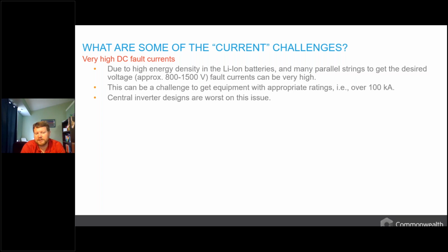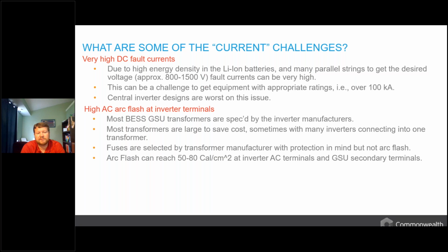So we see typical ranges that the inverter manufacturers are targeting for DC maximum voltages. The problem is, if we're limited to 1500 volts and we're talking about megawatt size long duration batteries, the only way to get the energy required is to add more and more batteries in parallel. What happens when you do that is, under short circuit conditions, these lithium ion batteries are very low impedance, and they can result in very, very high fault currents. The only thing that really protects us, or even limits us a little bit, is the collector system cabling, which is also designed to be very short. We'll talk about that in more detail as we proceed. We're also seeing that on the high DC fault currents, central inverter designs are what's driving this issue. It's the preferred methodology right now, mostly because central inverter designs allow us to do things like microgrid forming.